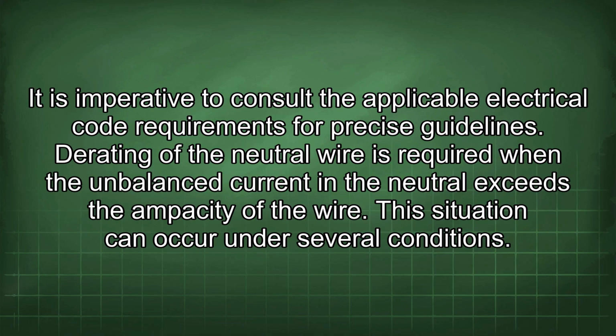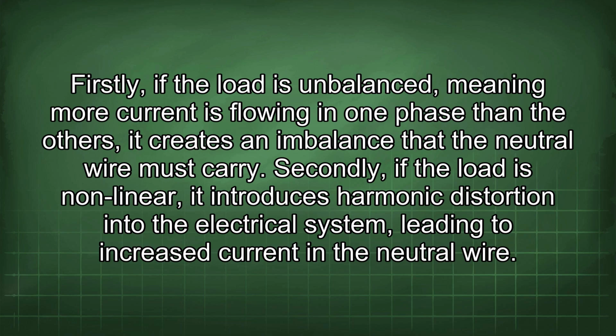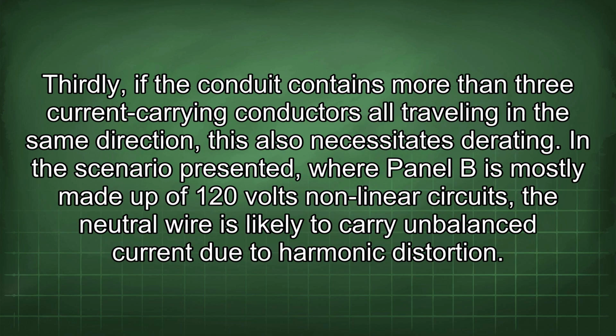It is imperative to consult the applicable electrical code requirements for precise guidelines. Derating of the neutral wire is required when the unbalanced current in the neutral exceeds the ampacity of the wire. This situation can occur under several conditions. Firstly, if the load is unbalanced, meaning more current is flowing in one phase than the others, it creates an imbalance that the neutral wire must carry. Secondly, if the load is nonlinear, it introduces harmonic distortion into the electrical system, leading to increased current in the neutral wire.